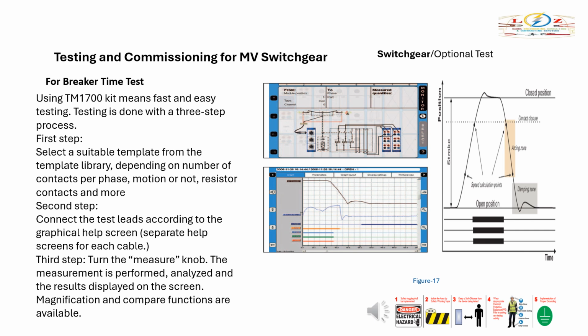It should also be noted that breakers that perform synchronized breaking must meet more stringent requirements. There are no generalized time limits for the time relationships between main and auxiliary contacts, but it is important to understand and check their operation. The purpose of an auxiliary contact is to close and open a circuit. Such a circuit might enable a closing coil when a breaker is about to perform a closing operation and then open the circuit immediately after the operation starts, thereby preventing coil burnout.